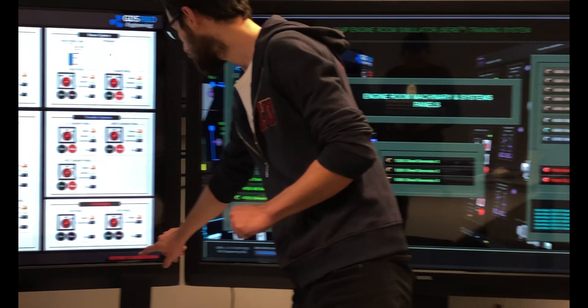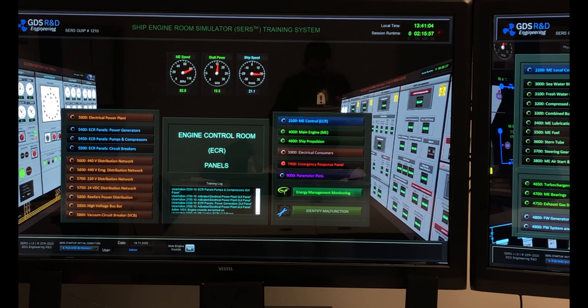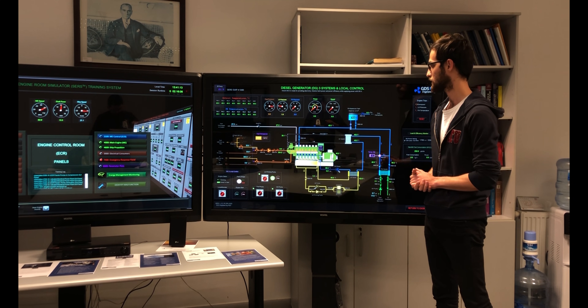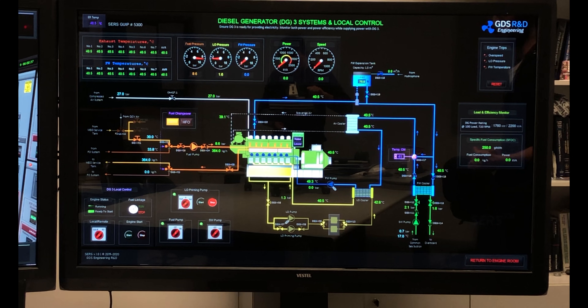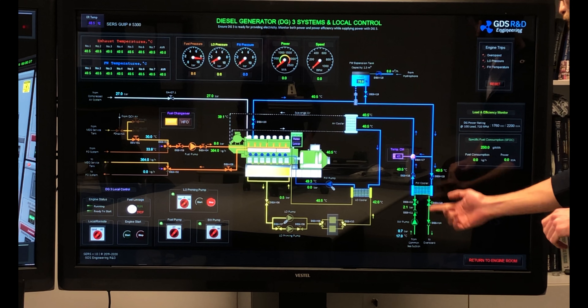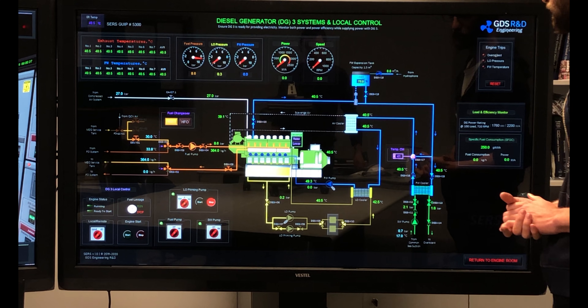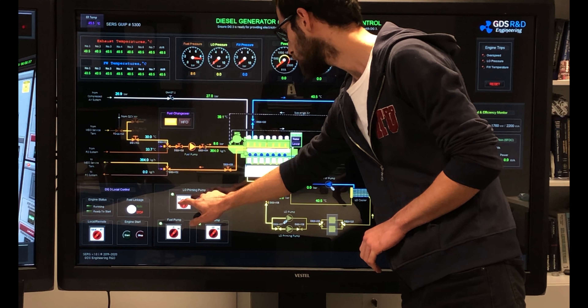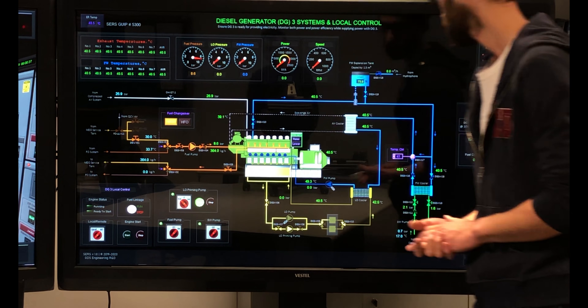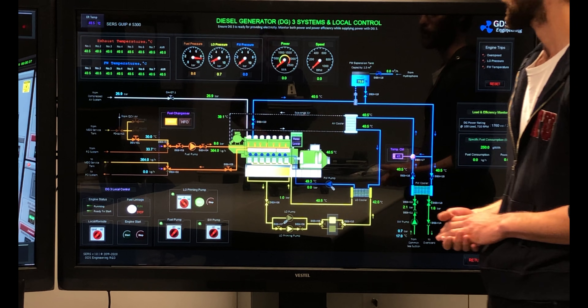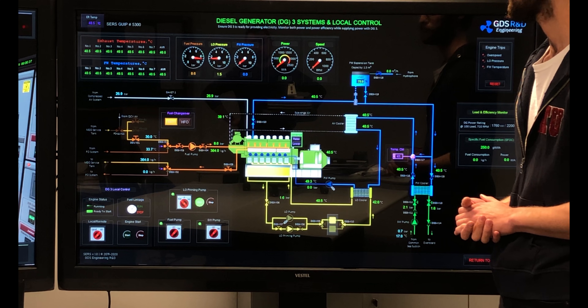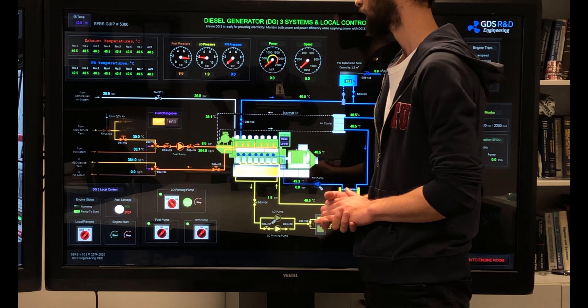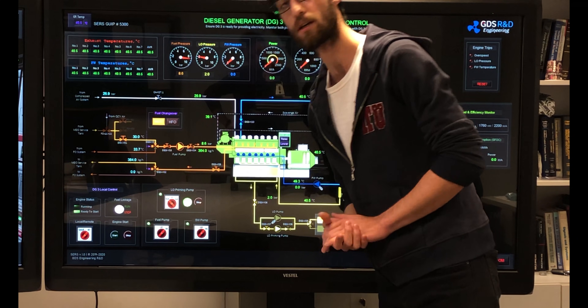Now I will start diesel generator number three and feed the bus bar with it. Here are diesel generator panels one, two, and three, and I am pressing the number three screen. I am checking the systems and confirm that the seawater system and freshwater system are in operation, and the lubricating oil system is lined up. I will start the lube oil priming pump in manual operation mode. I am observing the lube oil pressure on the gauge — I have 8.6 bar for lube oil pressure and enough pressure for start air.